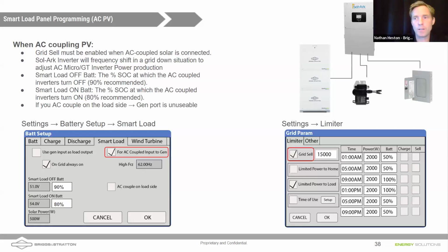We call that frequency shifting. Another thing that we can do with the Sol-Ark is have it completely turn off battery charging when that battery gets full. Notice that anytime the batteries are above 90%, this setting would turn off battery charging from those smart loads. The way it does that is it cuts the gen port off. The power coming in from the microinverters gets cut completely.